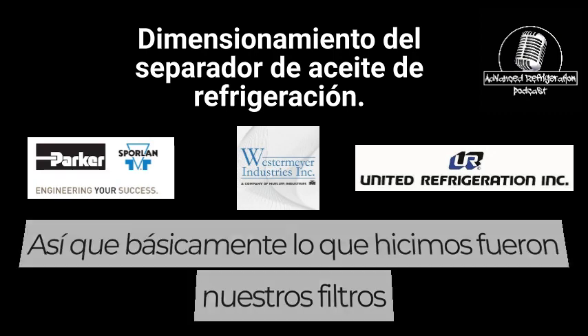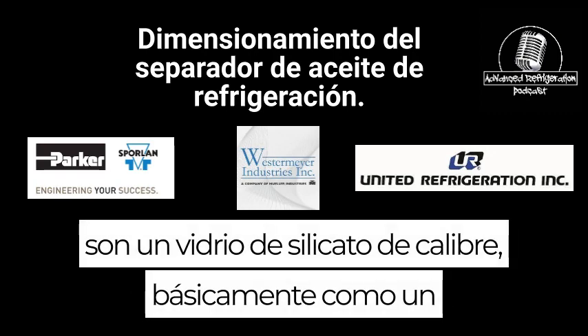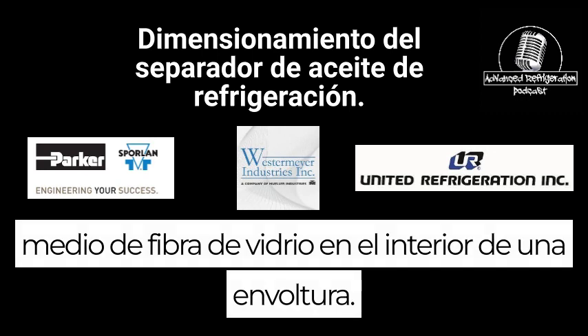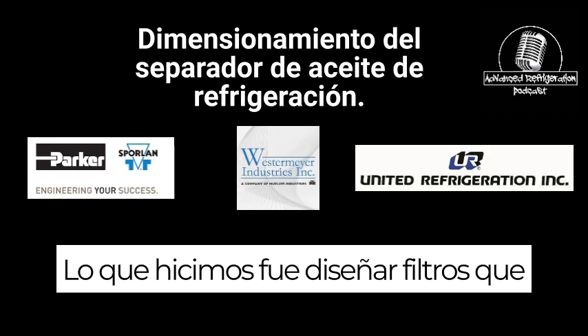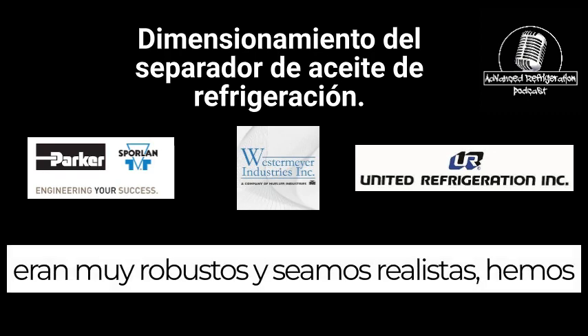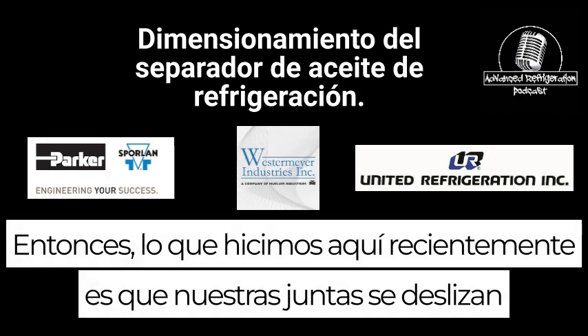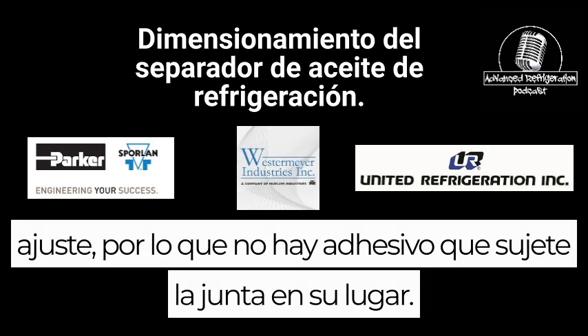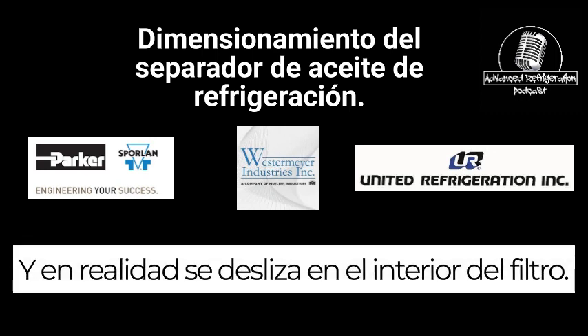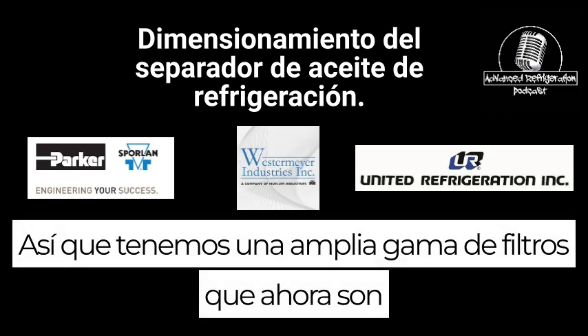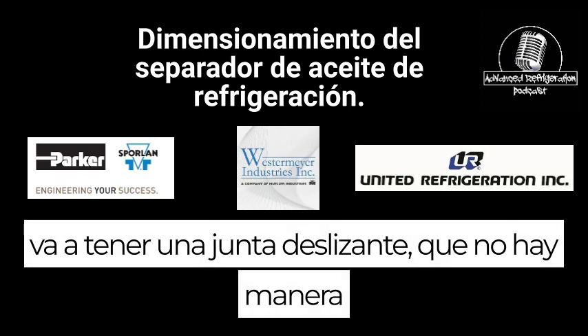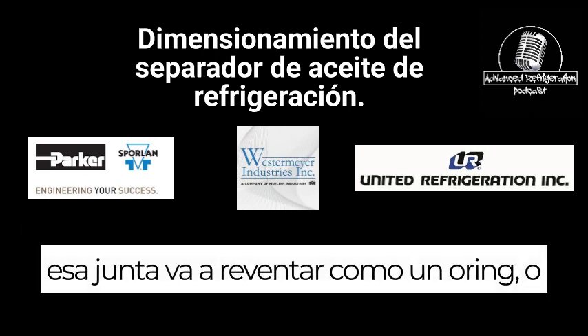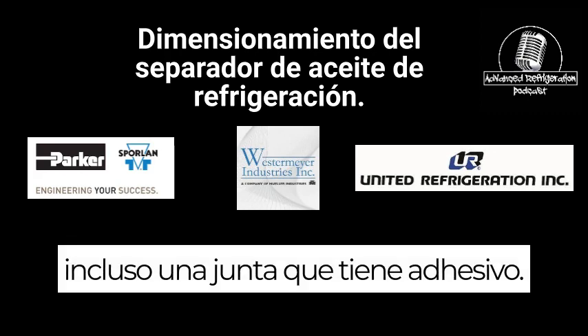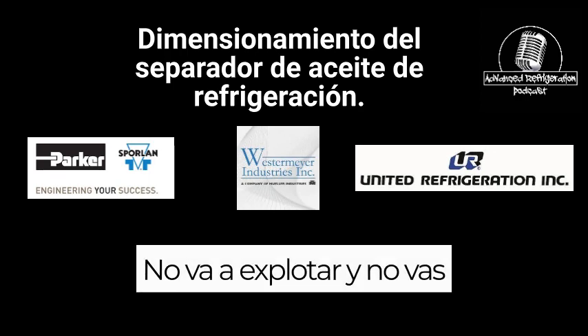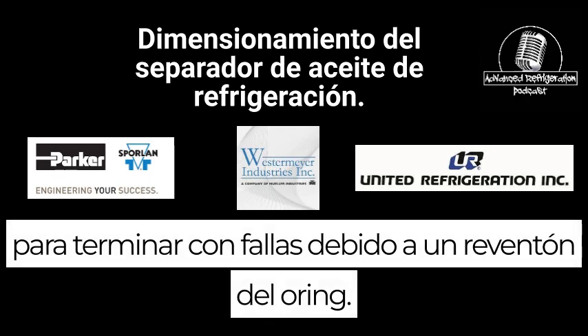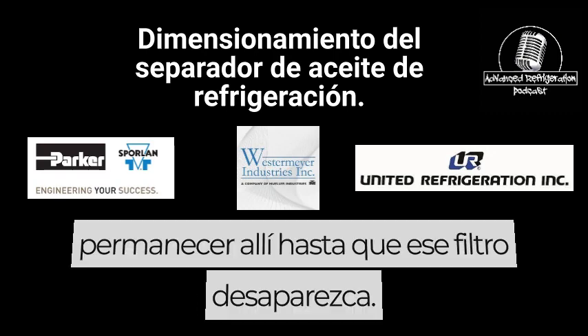Sure. Basically our filters are a borosilicate glass, like a fiberglass media on the inside of a wrap. We designed filters that were very robust, and let's face it, we've all had our heartburn with gaskets. So what we did here recently is our gaskets are slip fit. There's no adhesive holding the gasket in place, and it actually slips on the inside of the filter. We have a wide range of filters that now have a slip fit gasket, so there's no way that gasket is going to blow out like an O-ring or even a gasket that's got adhesive on it. You're not going to end up with failures due to just an O-ring blowout. Once it's torqued, it's going to stay there until that filter goes.